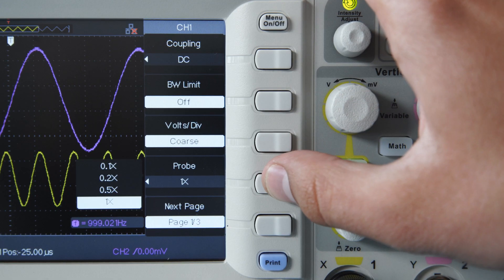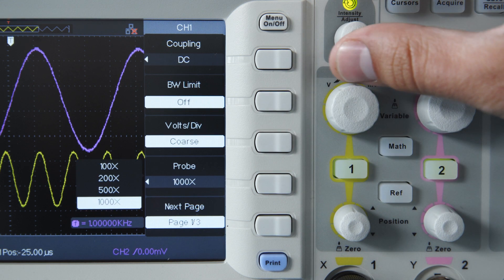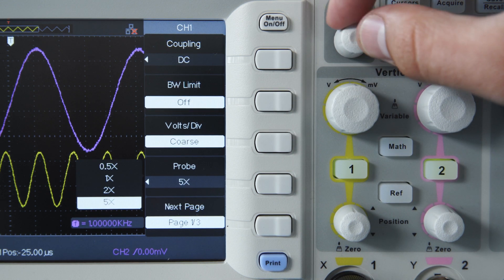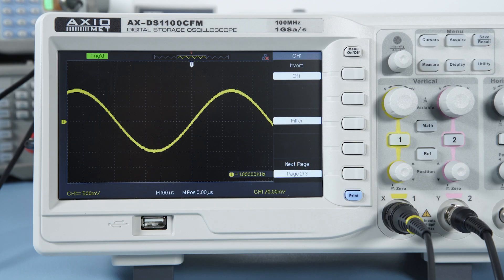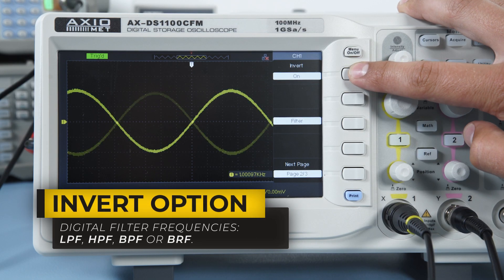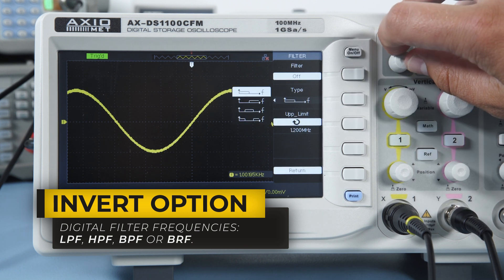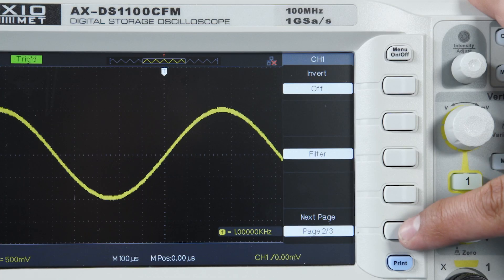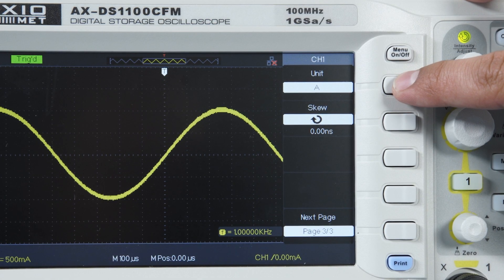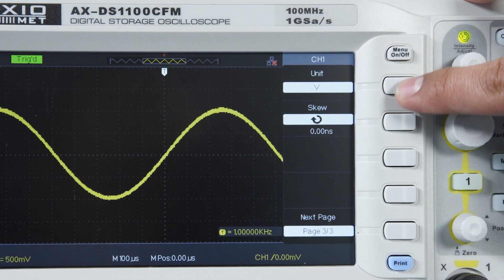Use the Universal knob to set probe attenuation ratio between 0.1 and 10,000. On the second page, we can find the Invert option and you can set a digital filter with the desired frequencies. On the last page, you can change volts to amperes or perform a skew correction.